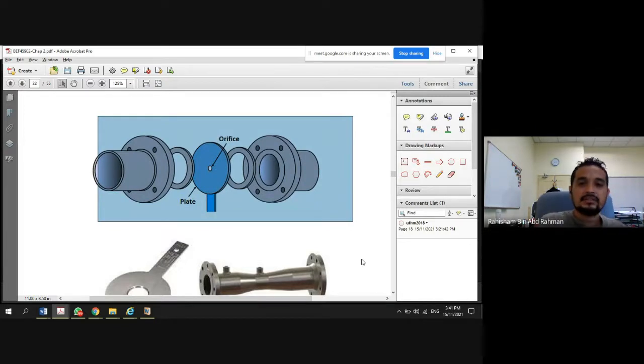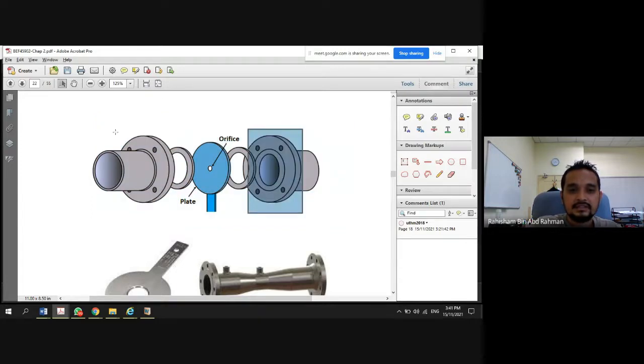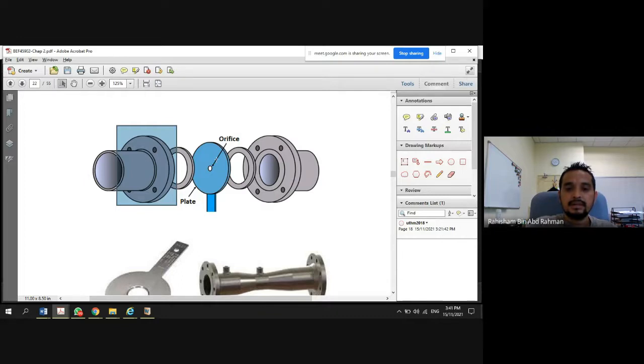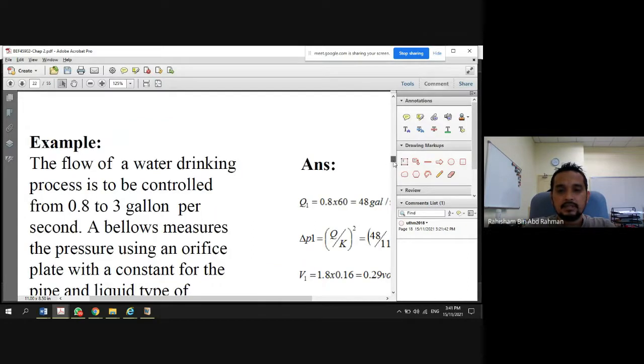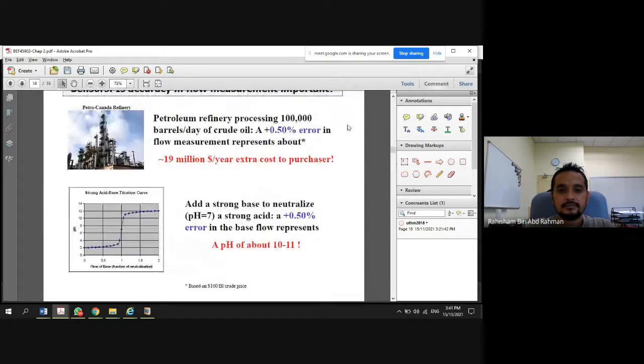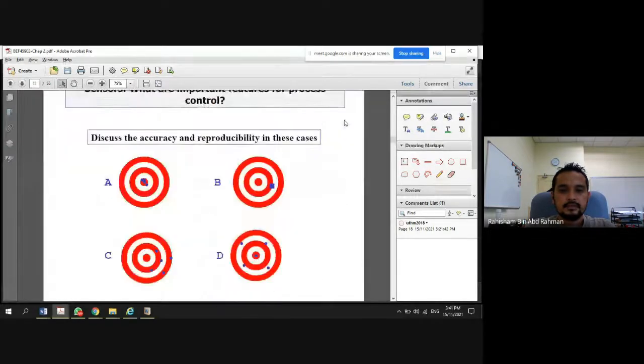Okay, that is the reason, if you notice, that in a power plant, oil and gas, you can see there are too many of these flanges, the pipe ends like this, because they want to put in the orifice plate or a measurement device so that they can measure the flow rate. That's why we rarely see a joint in one straight line within process control, within the power plant. There are too many of them.